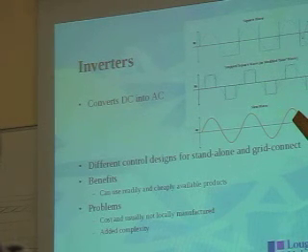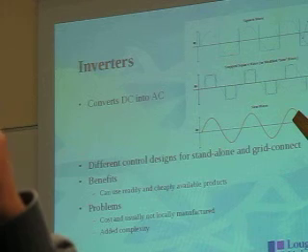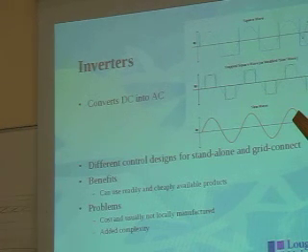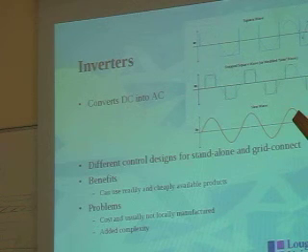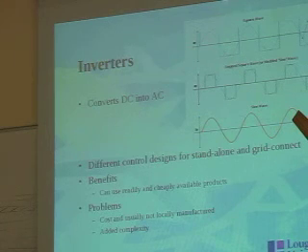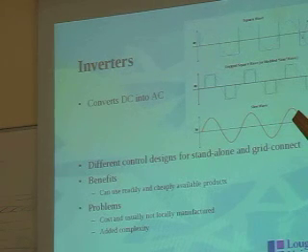Why is the stepped one better? It gets rid of what's called the third harmonic. If you did a Fourier transform and looked at the frequency spectrum of that square wave, you would see the square wave is actually made from thousands and thousands of sine waves on top of each other. You get what's called the third harmonic, which in a square wave inverter is very high. Third harmonic causes heating, which is not useful. It's lost energy. So the stepped square wave reduces the size of the third harmonic, but not much else. So that's why we use it.